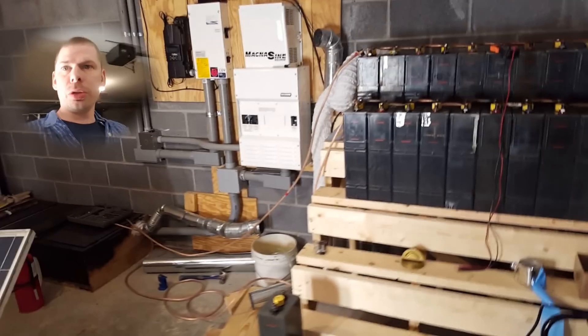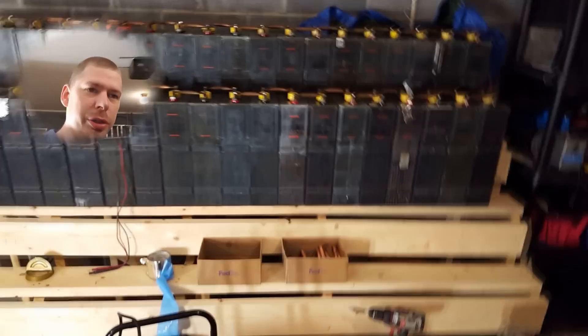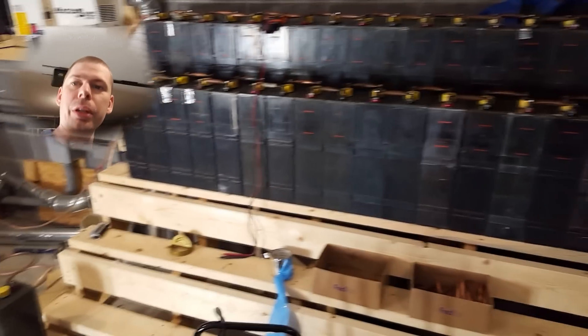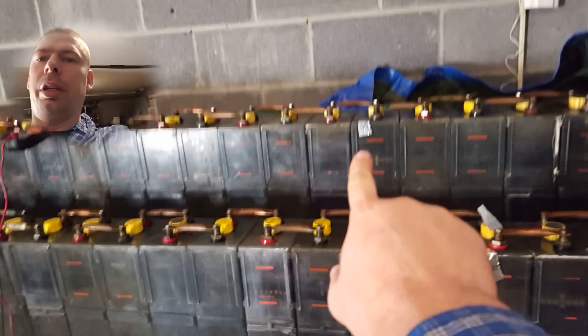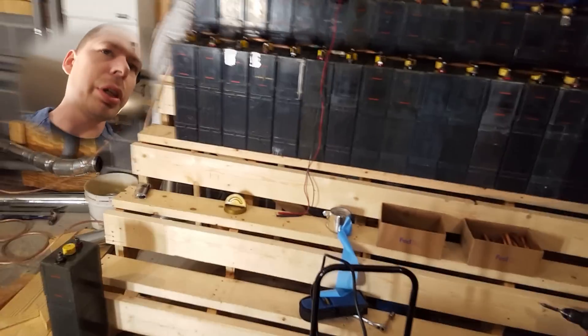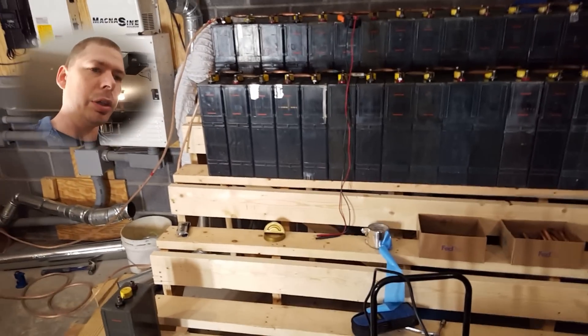What's up everybody, it's Philip 20 day. We've got some batteries — this is 38 batteries in series as one bank. You can see I've got markings on them, temporary markings. I've got this one, that one there, those two, and that one right there — those are currently very low voltage during a load test.